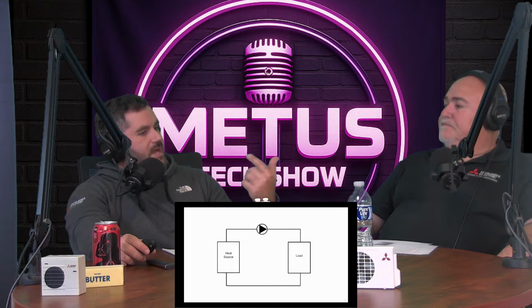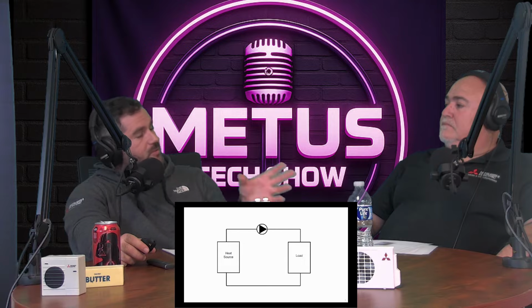We actually worked on some pellet boilers. So a wood pellet boiler, really similar premise, except typically when we would install them, it was all going to a very large buffer tank. So it was just like your typical pellet stove you'd have in your house, where there's a hot surface ignition that's initially sparking the dry wood pellets, and then there's an auger in there that's adding pellets as we go, and then there's a sweeper arm that keeps the soot, or the fines, from collecting. But all the water that gets heated from that heat actually just goes into a large buffer tank.